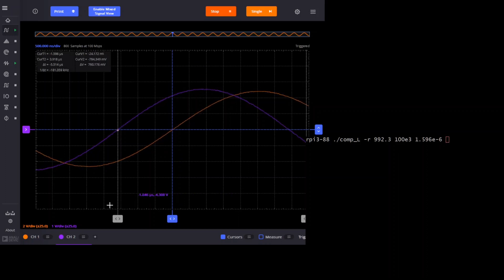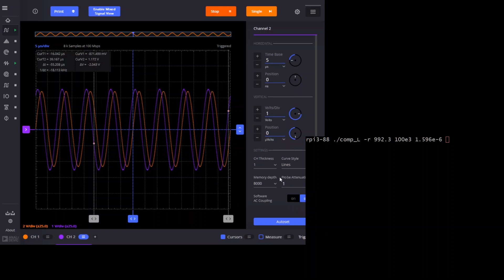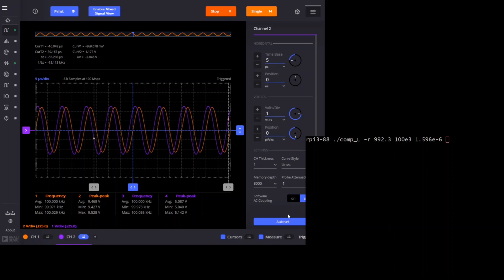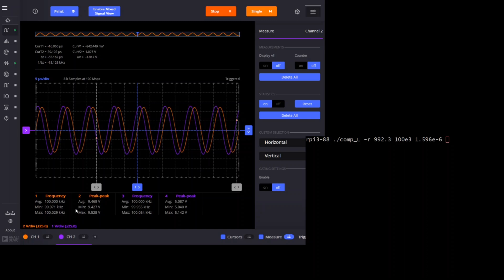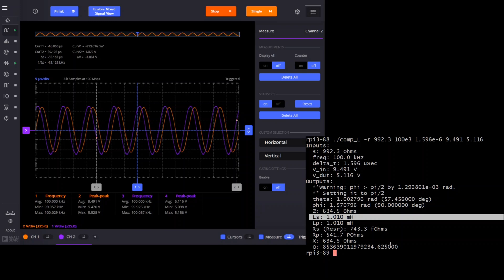Now we measure the amplitude of the signals. I'll change the time base to get more signal to measure, then go to the measurement menu. We're using Scopy statistics, which gives us the benefit of averaging. I do a reset to make sure I haven't been averaging something from before. We can verify our frequency is 100 kilohertz, and we see the amplitude of VIN and the amplitude of VDUT. So we enter those: 9.491 for VIN and 5.116 for VDUT. The computation is done by my program, and we can see our inductor measures as 1.01 millihenries — which is spot on. That's a good measurement.